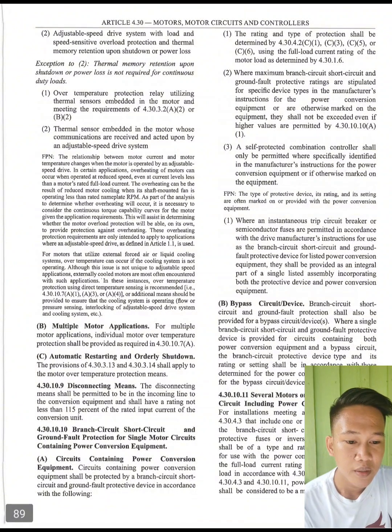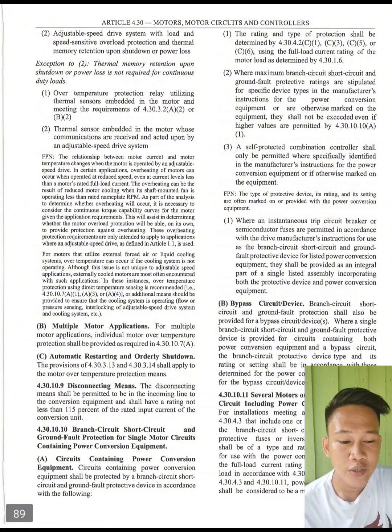Second, bypass circuit device, branch circuit, short circuit, and ground fault protection shall also be provided for a bypass circuit devices, where a single branch circuit, short circuit, and ground fault protective device is provided for circuits containing both power conversion equipment and a bypass circuit. The branch circuit protective device type and its rating or setting shall be in accordance with those determined for the power conversion equipment and for the bypass circuit devices equipment.